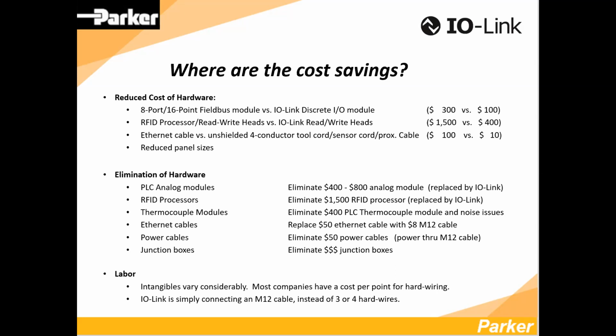You have thermocouple modules in PLCs that are expensive. There are solutions out there for wiring thermocouples into a thermocouple module - it's an IOLink module. Again, we talked about the Ethernet and power cables, and junction boxes, a lot, can traditionally just be eliminated as well.